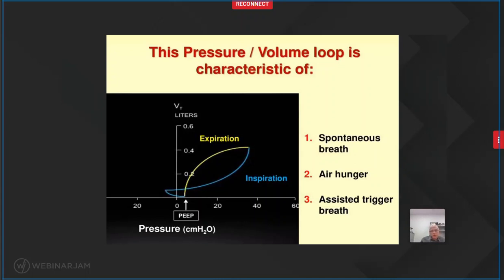The reason I know that is because you can see here that the initial change in pressure goes in the opposite direction. The inspiration doesn't go up right away, but it goes negative. So this breath is triggered by the baby. It's not completely a spontaneous breath because it becomes positive again. So this is a breath that was triggered by the baby, but it was assisted by the ventilator. This is what we call the fishtail. When you see this small fishtail here, it means that the breath was triggered by the infant. This little tail should not be too big. If it's too big, it means that the baby is making too much effort, maybe because the triggering is not appropriate, or you don't have enough flow, and that's why this loop could become quite large, and you have to look at that too. So it should be a small fishtail that triggers every single breath. That's the one you want to see.